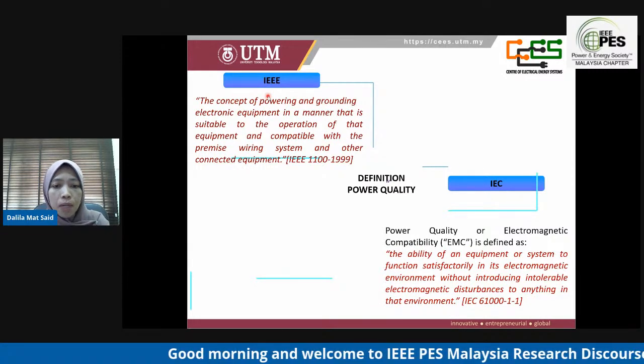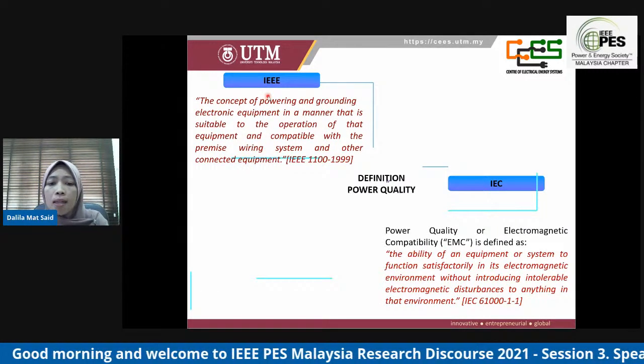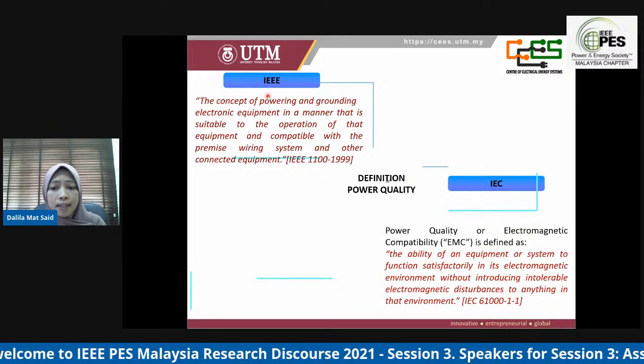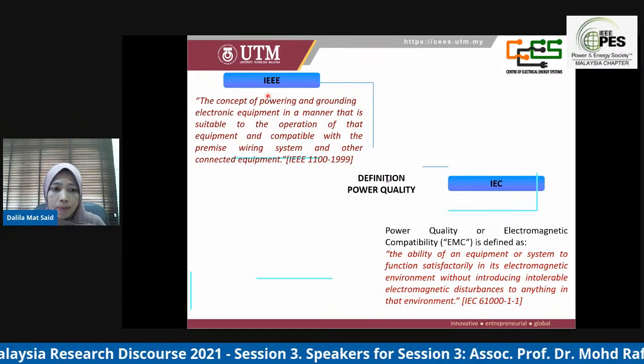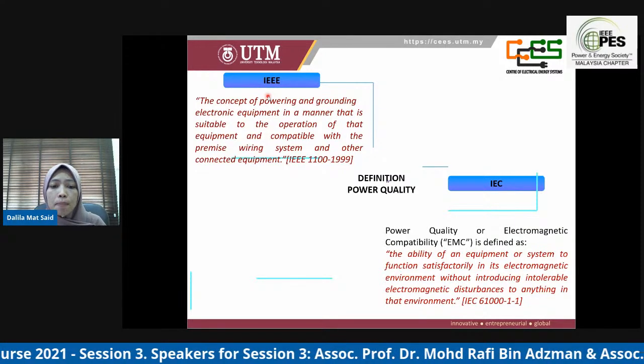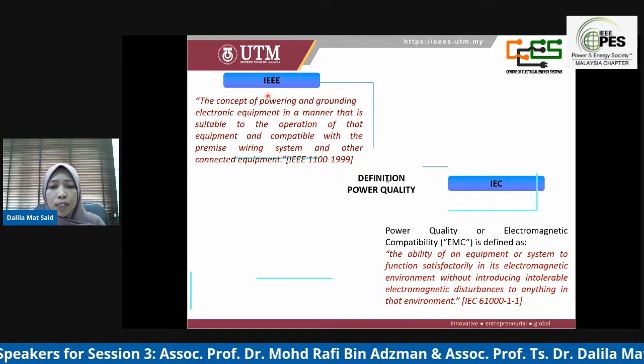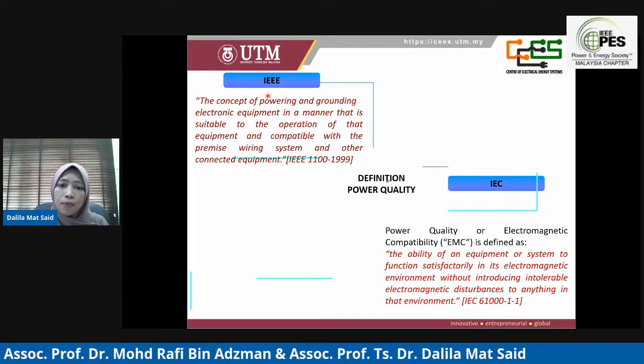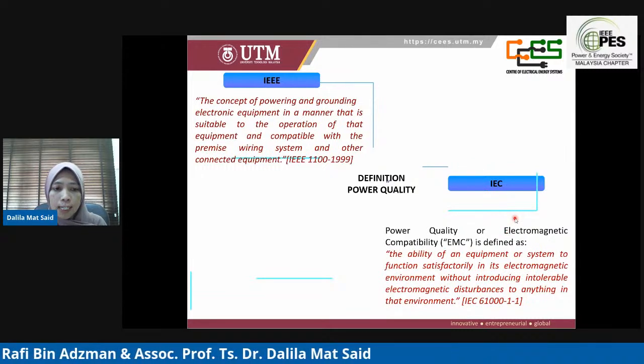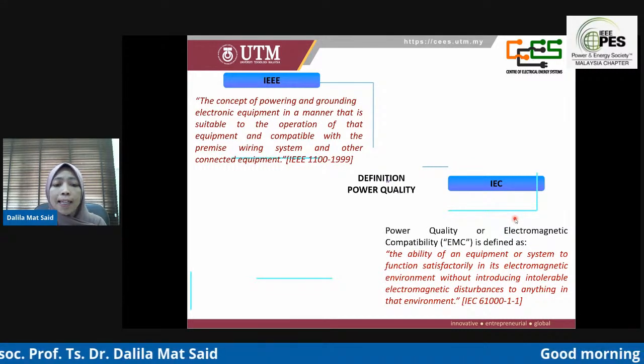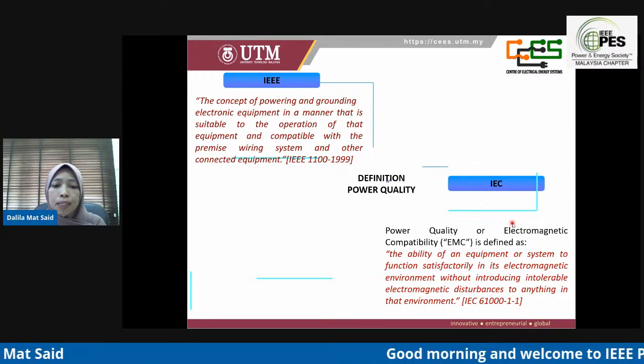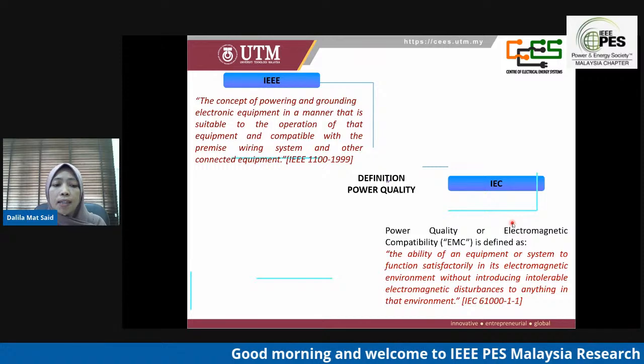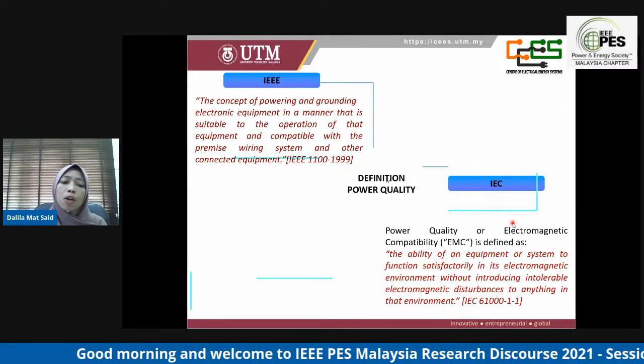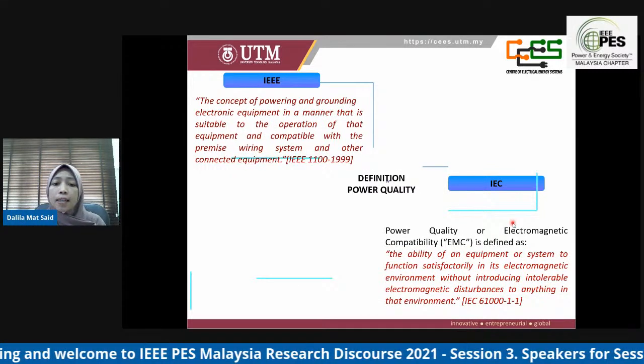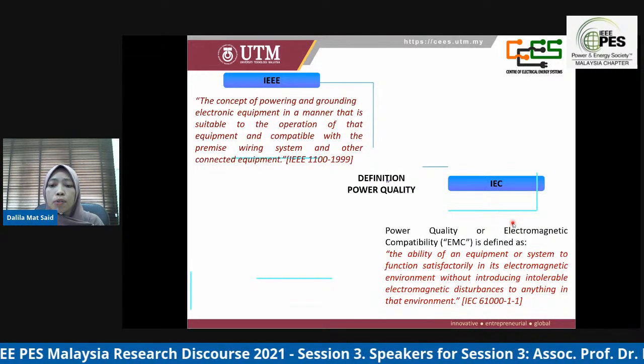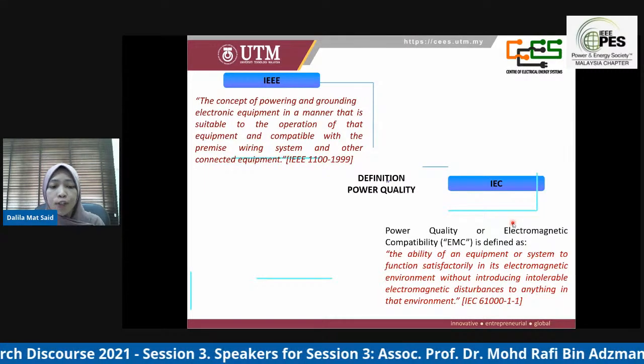Power and equipment being suitable for each other also means that there must be compatibility between the electrical system and the equipment it powers. They should also be compatible between devices that share the electrical distribution space. Referring to the IEC, the term used is electromagnetic compatibility. Electromagnetic compatibility is defined as the ability of an equipment or system to function satisfactorily in its electromagnetic environment without introducing electromagnetic disturbance to anything in that environment.